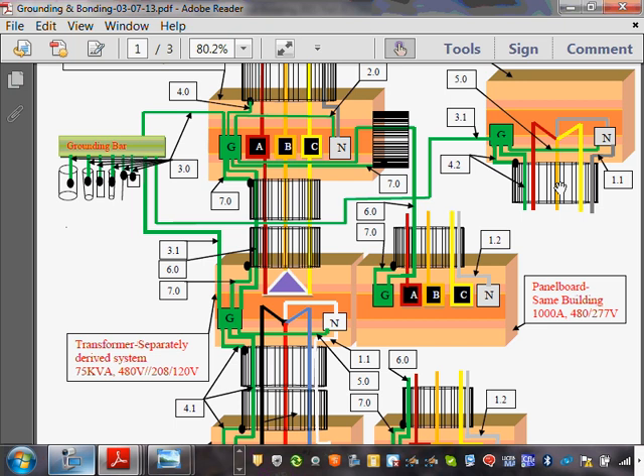Because the neutral is supposed to carry the unbalanced current in the three phases. If everything is three phase, everything's balanced, right? There's nothing to go back to the neutral. If you tie one line to 277, then the other current is going to go back to the neutral. If you don't have a neutral, no problem, it will work. But the current is going to go back through the grounding electrode system back to the source.